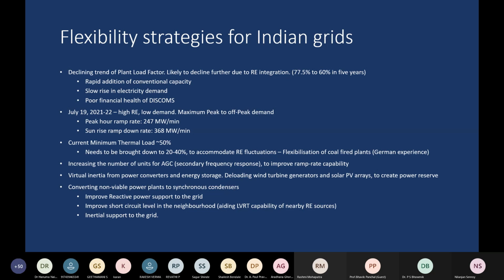So as a result, in the evening, when the sun sets and the solar drops, the drop in the solar will have to be compensated by increasing the power generation from other flexible resources. And the peak hour ramp rate is expected to be about 247 megawatts per minute. And this is very, very high ramping up.